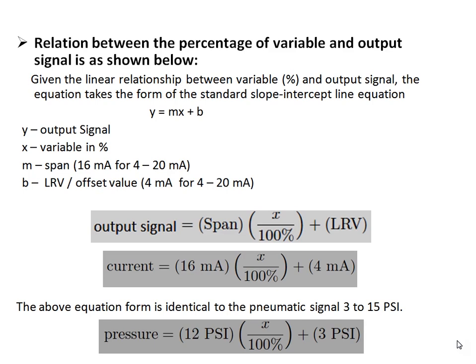The output signal equation is: output signal = span × percentage variable + lower range value. For 4 to 20 mA current output, this becomes: current = 16 mA × percentage variable + 4 mA. This form is identical to the pneumatic signal output of 3 to 15 PSI, which takes the form: pressure = 12 PSI (the span) × percentage of variable + 3 PSI, which is the low range value.